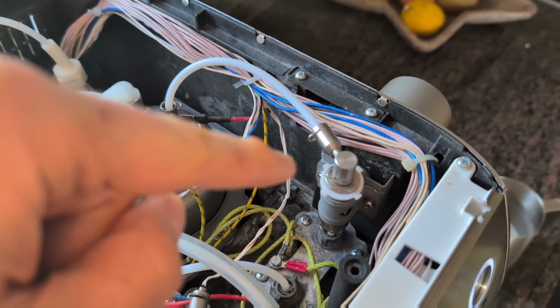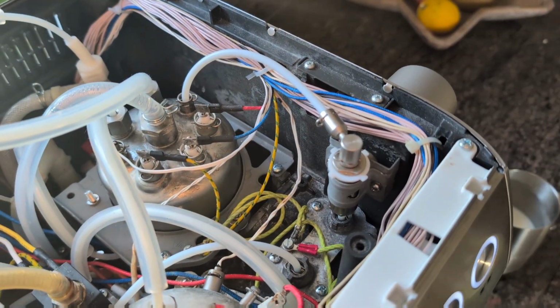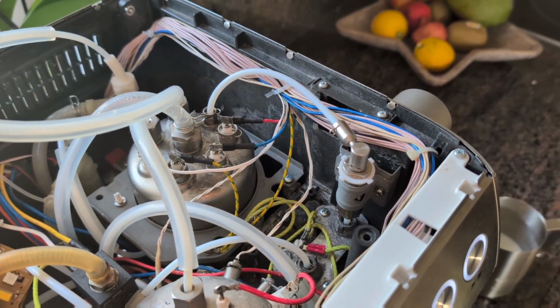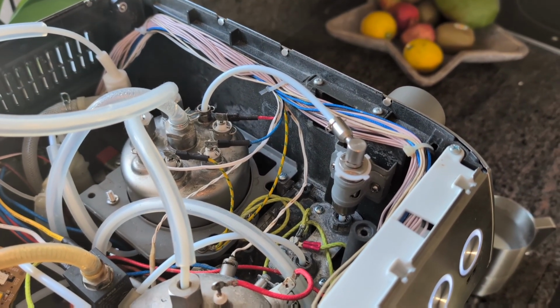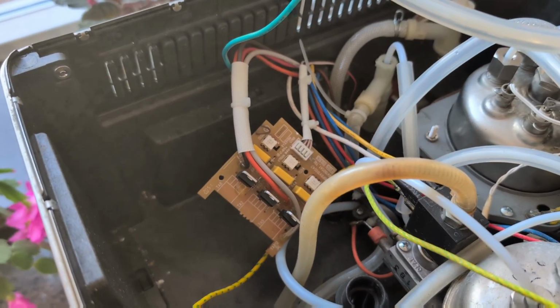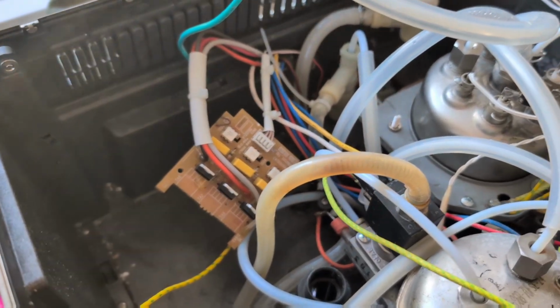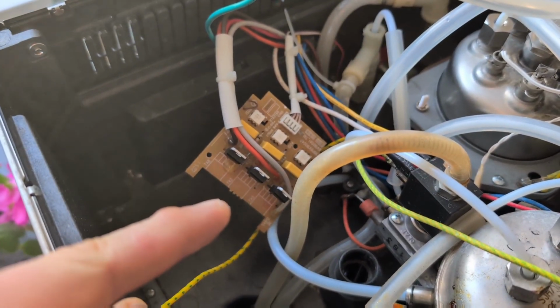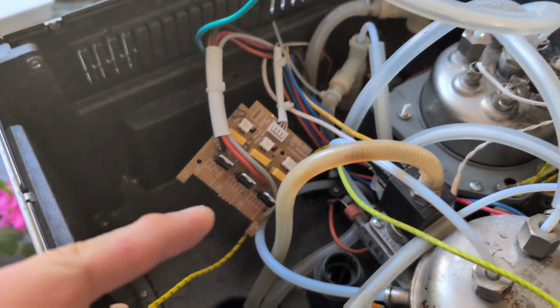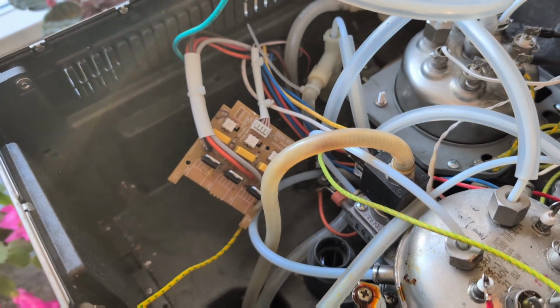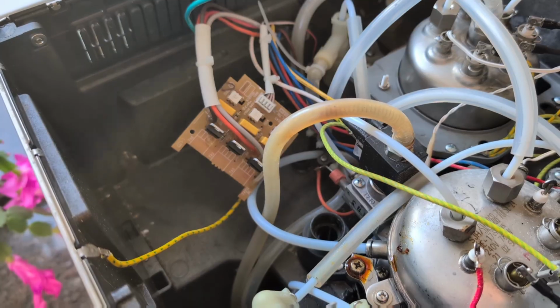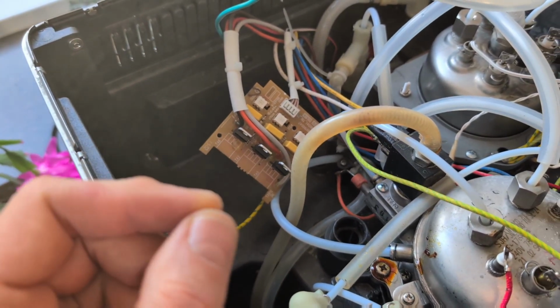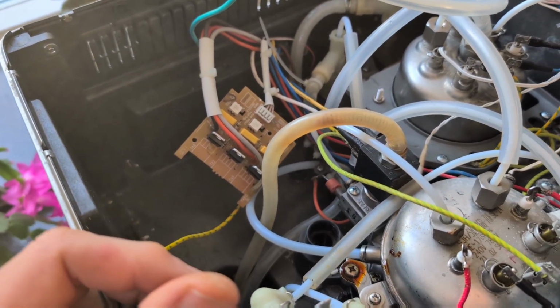I serviced the valve, and the valve is also good. I'm going to replace the PTFE gaskets later, but for now it's fine. The board is like new. There was an issue where the rightmost component, responsible for group head heating, was short circuited, but I fixed that, and the group head is heating properly now.